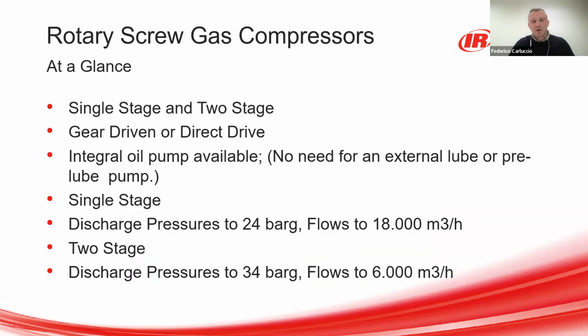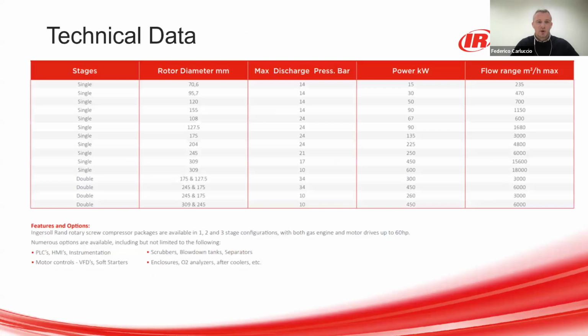In the next slide, you can see some of the features of our block compressors. They can be gear driven or direct driven. There's no need for an external lube or pre-lube pump. There's one internal that we can deliver if the occasion demands. For the one-stage solution, the maximum discharge pressure is 24 bar g, and the flow is 18,000 cubic meters per hour. For the two-stage solution, the maximum discharge pressure is 34 bar g, with a maximum flow of 6,000 cubic meters per hour. In the next chart, you will have a full view of the range of our equipment.